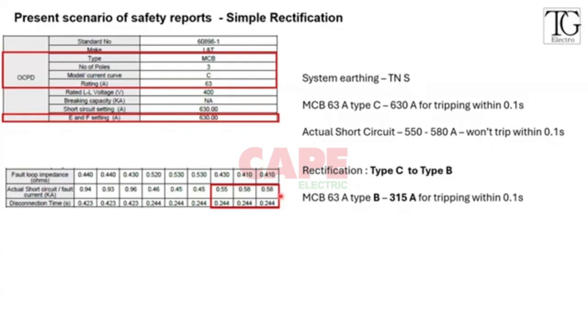And most of the faults coming in the industry are after the main circuit breakers, in the sub DBs where the wiring is not proper. In those areas only these faults are coming, and you don't need to make a very big change like rerouting the cable or all those things. In most of these scenarios, a simple change is well enough to have better protection. Now onto the site scenario.